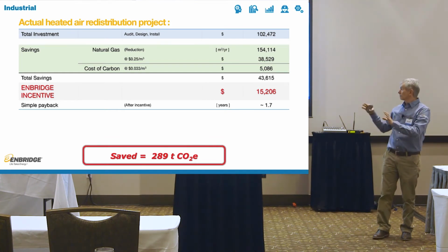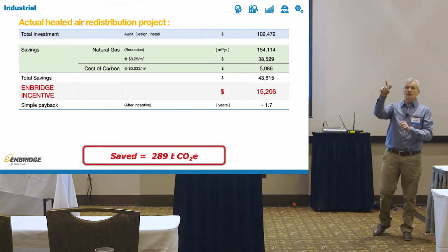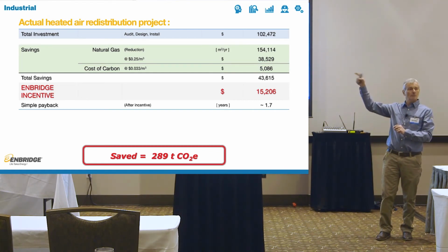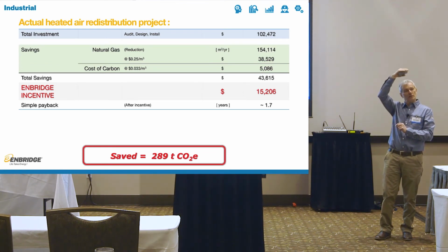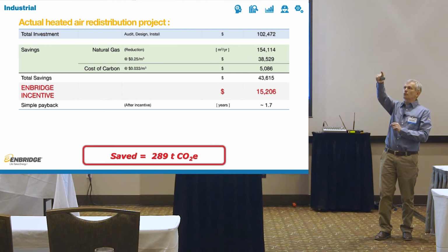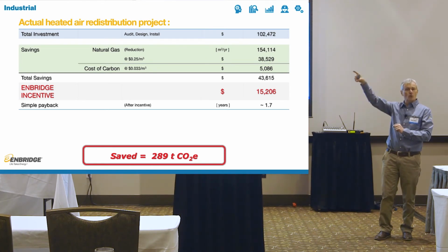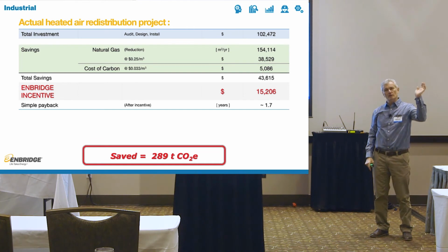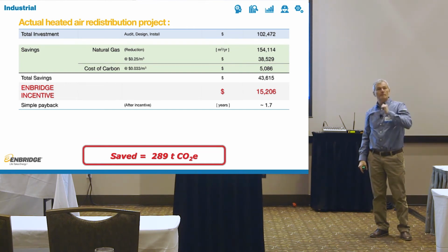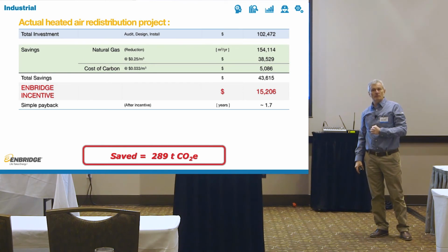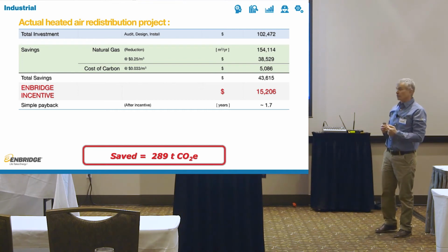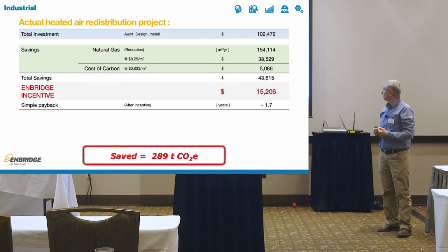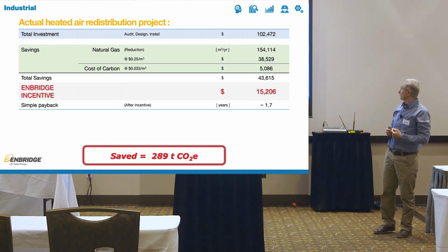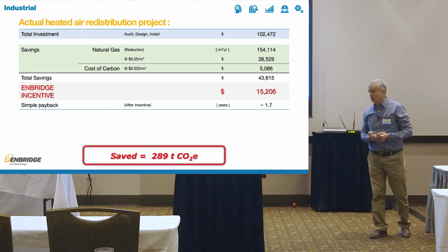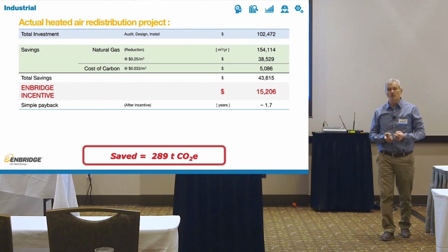So finally, they got hip to the game, and they said, okay, never mind. They drilled a whole bunch of holes in their wall between the two areas. And instead of exhausting that in the wintertime, they actually put a bunch of radial fans in those holes that took the air from the warm space and dumped it into the warehouse. Again, they didn't need any of the unit heaters anymore in the warehouse at all. They saved 154,000 cubic meters of natural gas. We gave them $15,000 in incentive for that, and they saved about 300 tons worth of CO2e in the process.